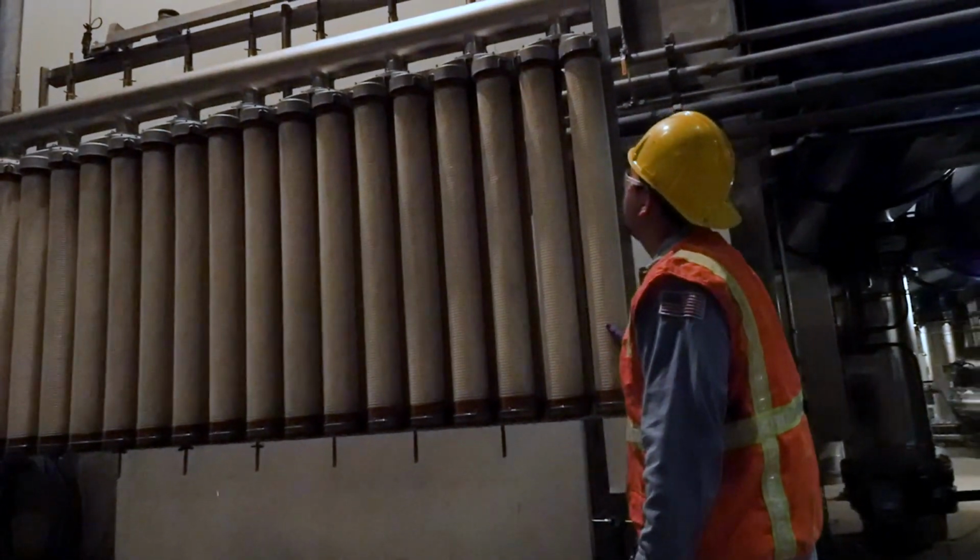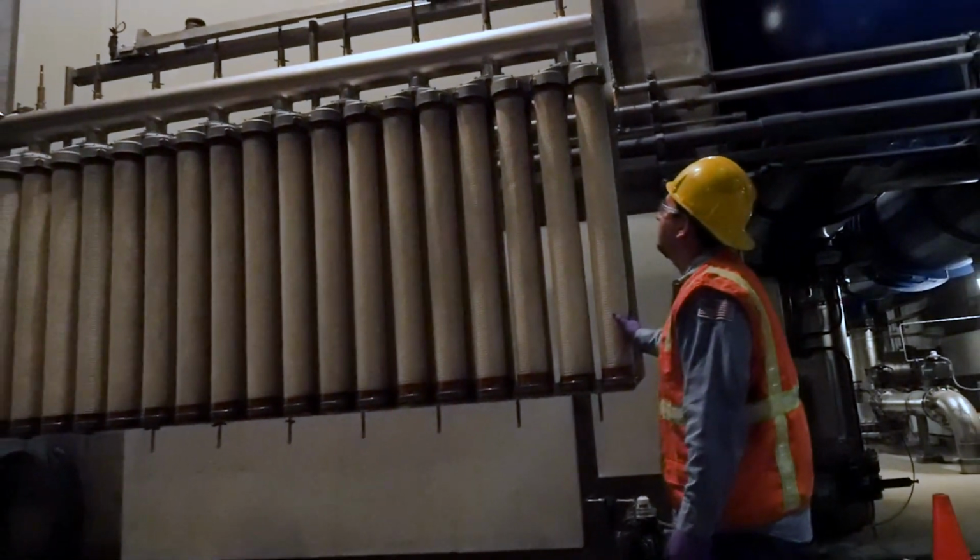Now, as long as we continue to backwash every 21 minutes and clean each cell every 21 days, these membrane modules will last for about 7 years, and then we have to replace them. So this continual process, as I said, is the first step in the process. It's an excellent pre-treatment for the reverse osmosis. So now we're going to head down into the basement first and take a look at the microfiltration. And then we'll head over to the reverse osmosis and then the UV. So why don't you follow me and we'll go downstairs and take a look at what we can find.